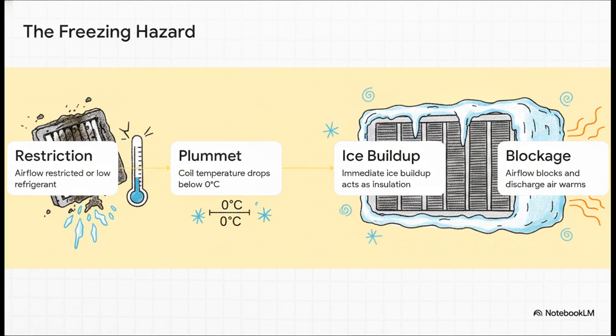Step 2, the coil instantly plummets below 0 degrees Celsius. Step 3, this causes rapid, immediate ice buildup on the coil. And since ice acts as an insulator, we hit step 4, airflow blocks completely, and the discharge temperature you feel rises right back up to room temperature. The machine is essentially suffocating itself.